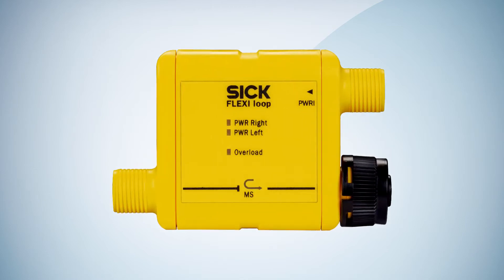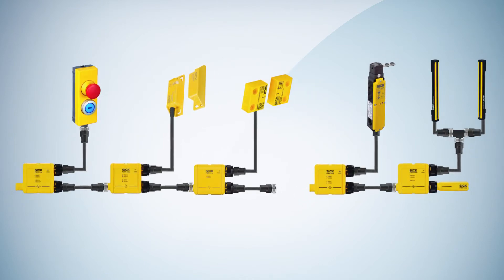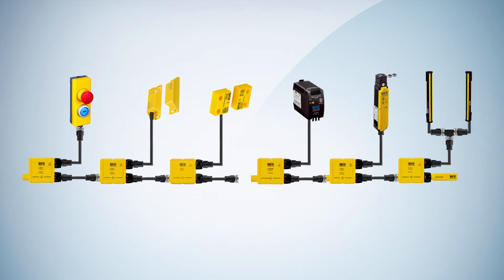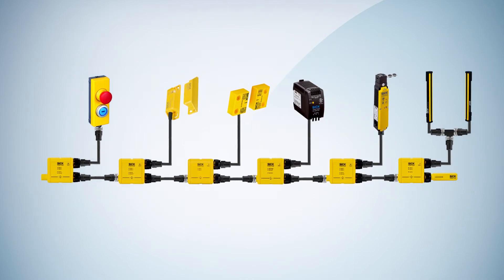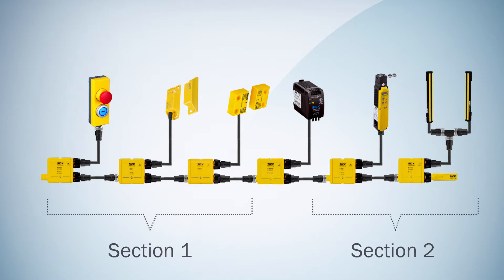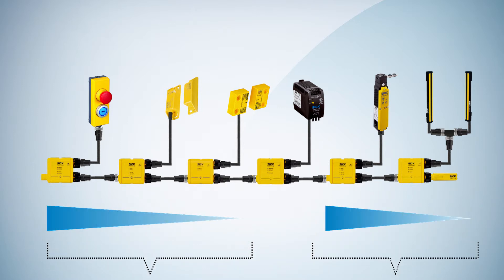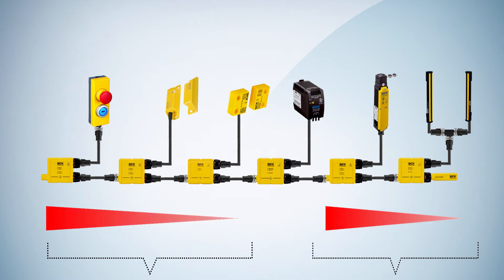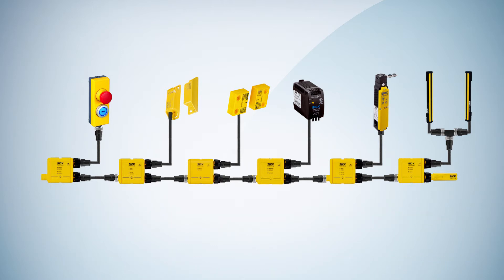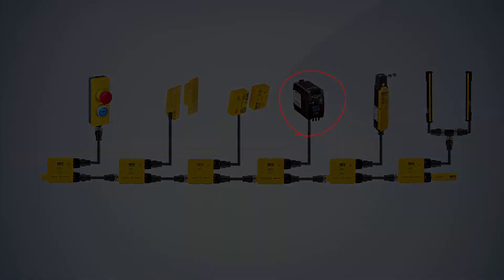Therefore, SICK offers an accessory module for FlexiLoop — the power injector — which can be added to your cascade at any point. Basically, the power injector accessory has three functions. First of all, it divides the loop into separate sections, thanks to its galvanic isolation. Moreover, it supplies the following section with power and protects it from overcurrent. Therefore, each section is then able to handle a maximum current of 4A. The power injector is connected to a 24V power supply or via a stop line directly to the cabinet.